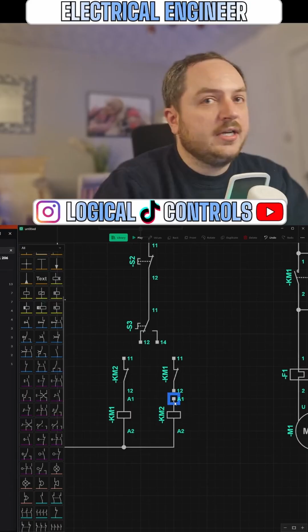KM2, so this is what's called an electrical interlock. If KM1 energizes, it's going to open up the contact over here to prevent KM2 from ever energizing. So you don't want the forward and reverse contactors on at the same time, because you're going to do damage. This all looks a bit messy, but I think we should be okay.